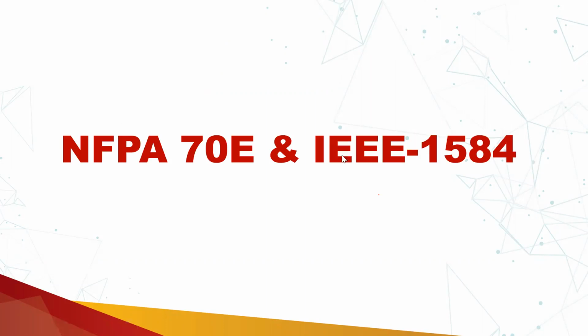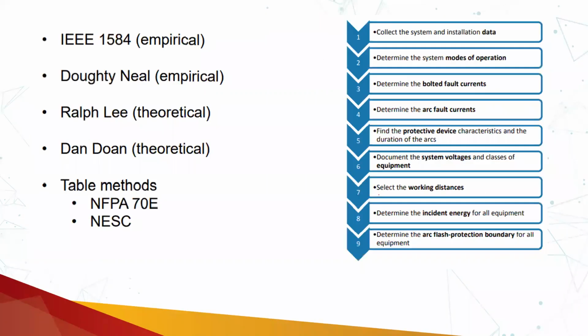A quick review about 70E and IEEE 1584, how they are similar, or how IEEE 1584 is part of Annexure D. In Annexure D you will find different methods to calculate the incident energy, and one of the methods is IEEE 1584, which is now being used globally. It has a few steps like collect the system and installation data, determine the system modes of operation - whether it is being operated in island mode and connection mode, or with tiebreaker off, on, etc.